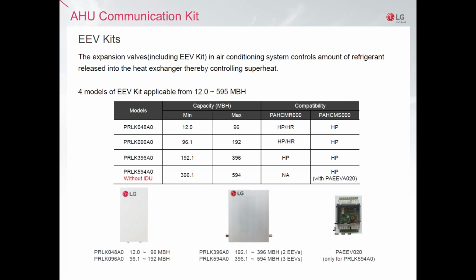The 048 has a minimum capacity of 12,000 BTUs and a maximum of 96,000. The 096 goes from 96 to 192, the 396 from 192 to 396, and the 594 from 396 minimum to 594 maximum. And they have different settings between those ranges so you can select the right size for the right combination, so they can match your application and the connected VRF unit's tonnage. The sizes 048 and 096 can be used in both heat pump and heat recovery applications, and all of them can work on heat pump applications. This might sound like we could have a shortage of capacity in the heat recovery options, but I will show you in upcoming slides why this is not the case.